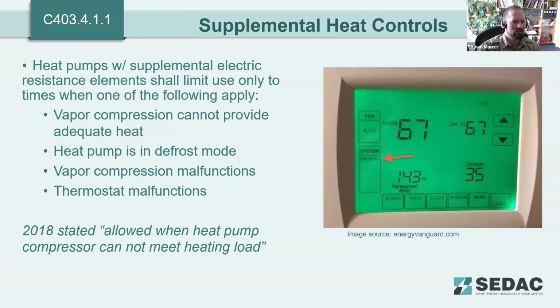Supplemental heat controls for buildings that are installing heat pump technologies. There is specific language regarding supplemental electric resistance heating for those units. Previously, the code had a pretty vague definition of when supplemental heat could kick on. It was just when the compressor couldn't supply the heat load. As it's now bullet pointed out, 4 bullet points that specifically state conditions when emergency heat can be applied using the control system. So when the compressor cannot provide adequate heating, so there's some sense that the system is running in heating mode, but it's not keeping up because the temperature is not increasing or has decreased at the thermostat, then you can kick on that supplemental heating. If the heat pump is in defrost mode, obviously the compressor is not supplying heat then, so the supplemental heat can kick in that instance. If the vapor compression system malfunctions, or the thermostat itself malfunctions and isn't adequately triggering that compression cycle of the heat pump.